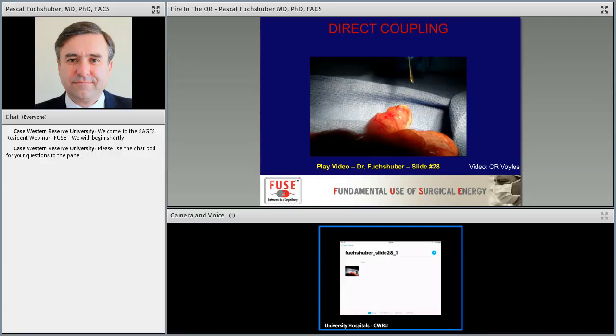It's such a small surface, the clip itself is so small that the current density, when you apply 4,000 volts with coag, is so high that you can reach temperatures of over 1,000 degrees. Now, you can guess what that does to the living tissue, and you can guess that if you do that long enough, you will destroy and necrotize the staple line and you might get a leak. And that's my assumption of what happened with this patient. And it will happen to you if you do that. So please don't do that.